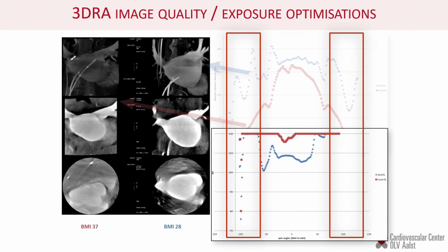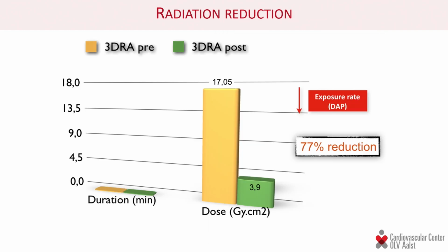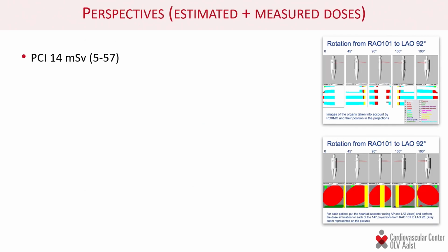And this is data from our detectors. Again, don't worry about the numbers, but what we realized is that the detector is shooting your patient full of photons and you are not getting a nice image as a result. So instead of trying to optimize our images, we told GE, forget about this and give us lower quality 3D angio. And this is precisely what you can do. You can dramatically reduce your patient exposure by accepting a very small, I would argue, almost invisible reduction in image quality. Again, for the purpose of understanding where the veins are, the quality is quite sufficient, as you will see.